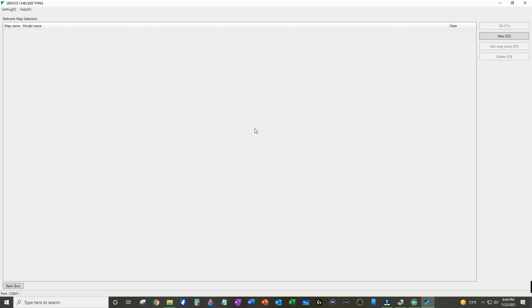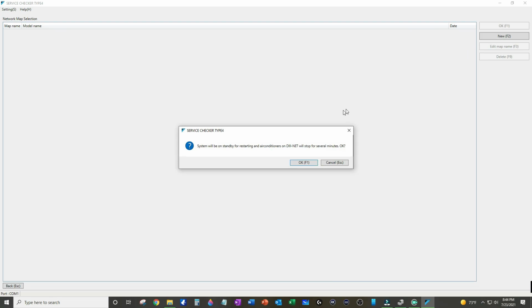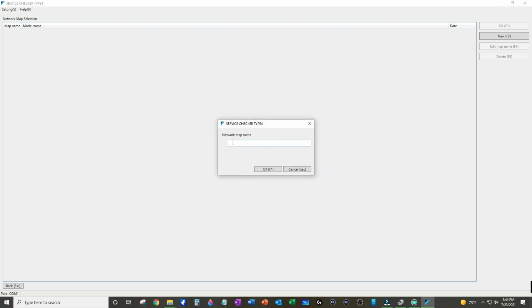Go ahead and click on New on the right-hand side of the screen, and a message window will display. This message basically says that when you connect the system, it will go into a brief standby period during the connection process. This is normal when connecting, so go ahead and click OK. When you click OK, you will be prompted to create the network map name. I will usually type in the job and what I'm doing.